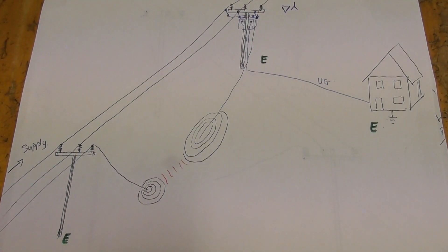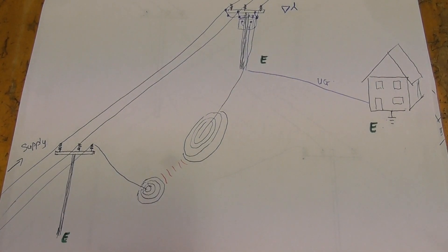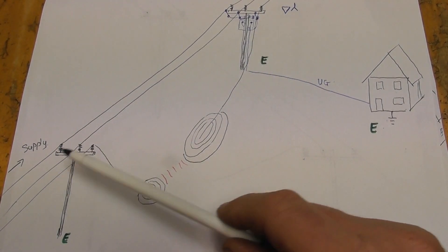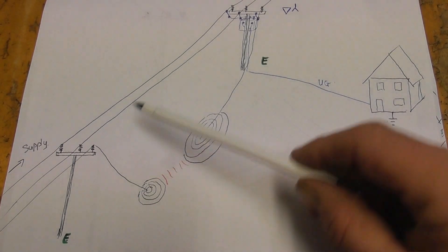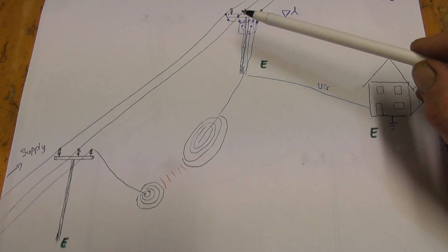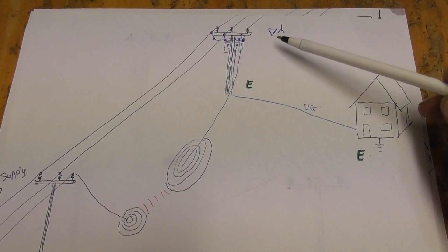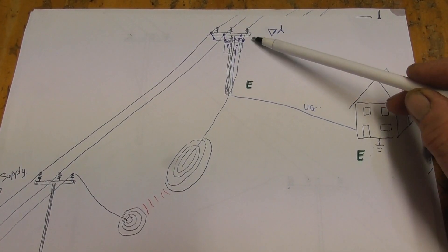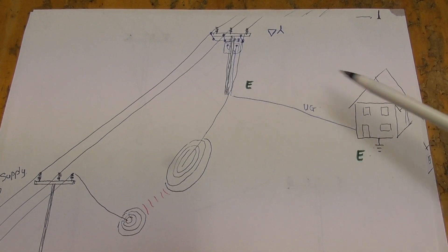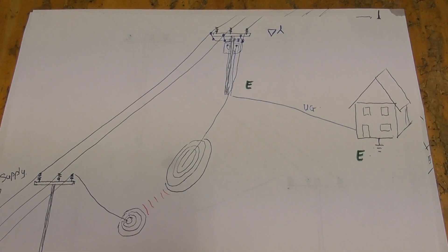The thing to mention is, if on a broken line with a three phase load, so the supply side is here. Feed is live, but also the power on the other side will go through the winding on the transformer, delta star usually. So the wire on the return pass will be live as well. That's a thing to take into account.